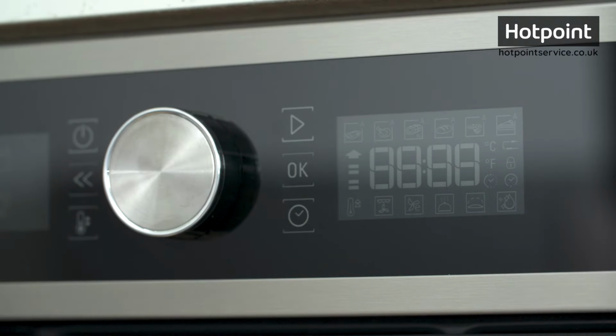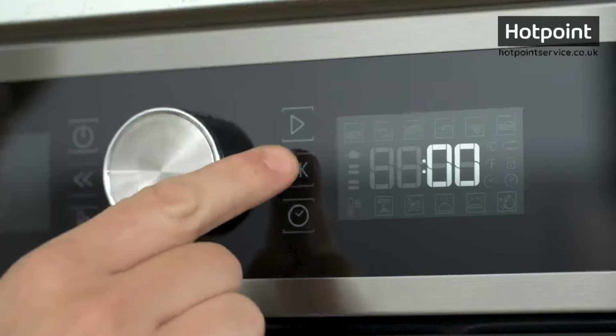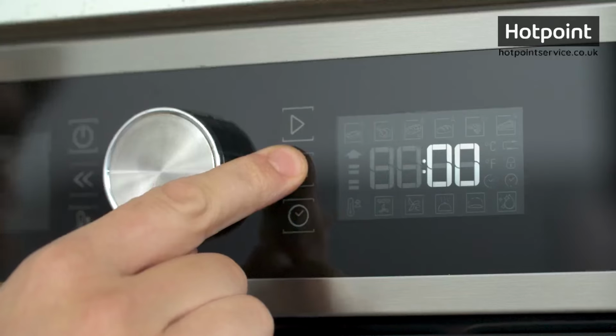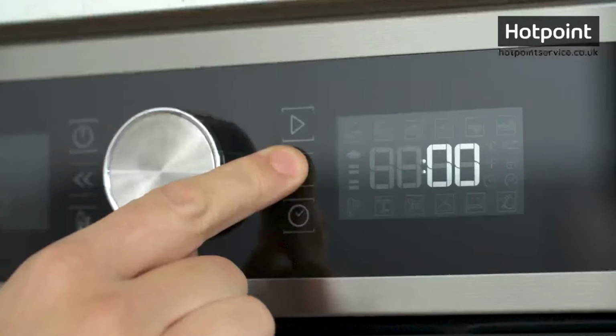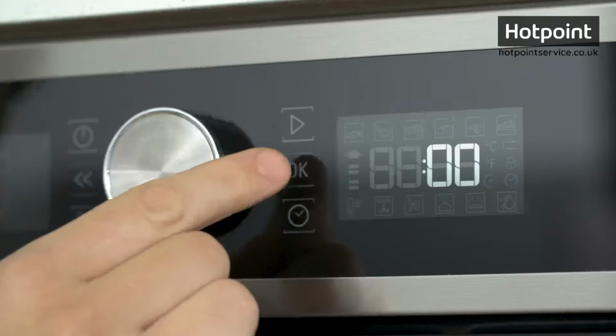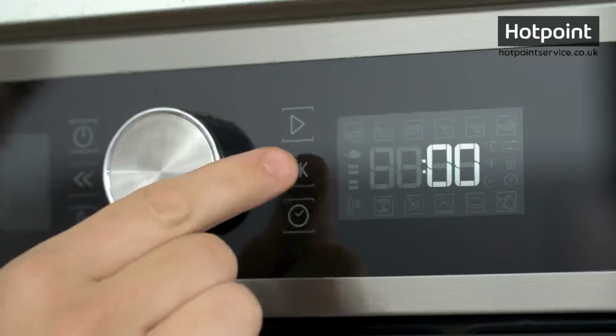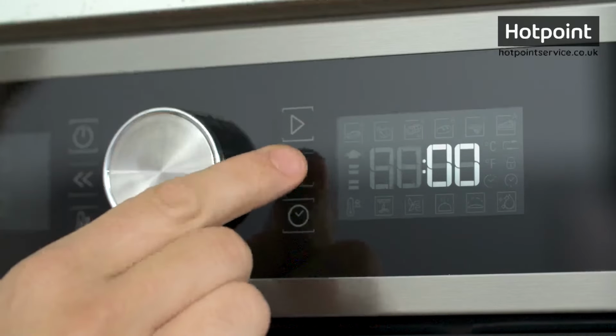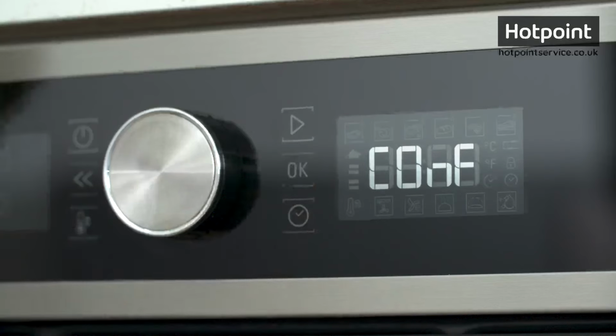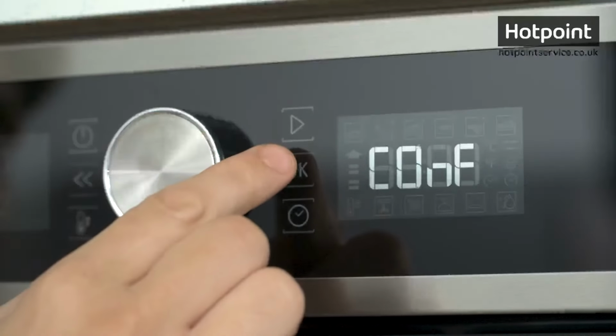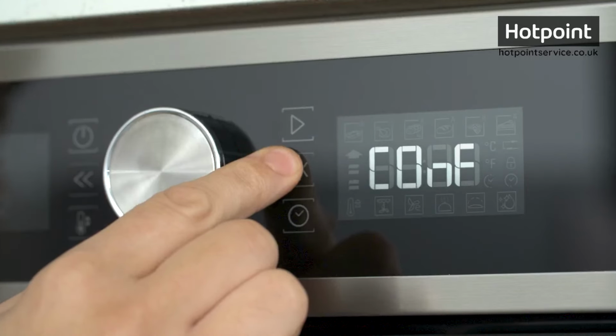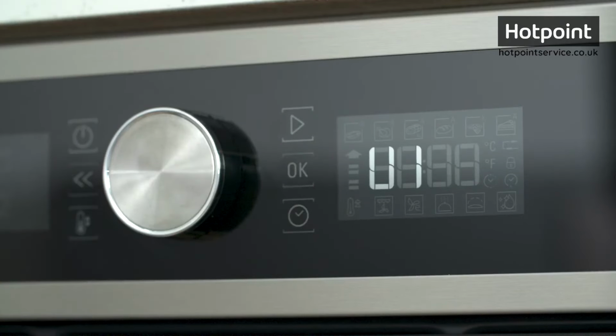Start by turning the power off for at least 30 seconds, then switch the machine back on again. Push and hold down the OK button, and after about 5 seconds, the machine will make a short beep. Push the OK button 4 more times within 15 seconds. 1, 2, 3, 4, and the word conf appears on the display.